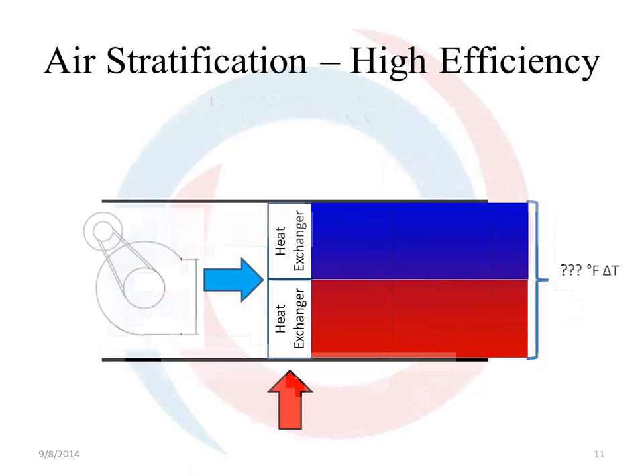Now, some other problems is the air stratification. At full load, it will be okay. But if you get down to around 40%, one of the heat exchangers is going to be kicking off. If it's the top one, in this particular case, you could have cold air at a part load condition, 35, 40 degrees coming out the top heat exchanger, and 70 degrees if it's a 100% makeup air unit coming out the bottom. This is going to really provide some comfort issues, unless you mix it well.